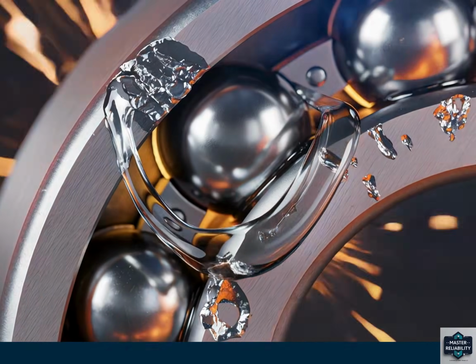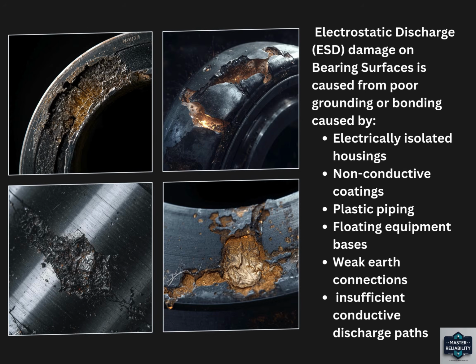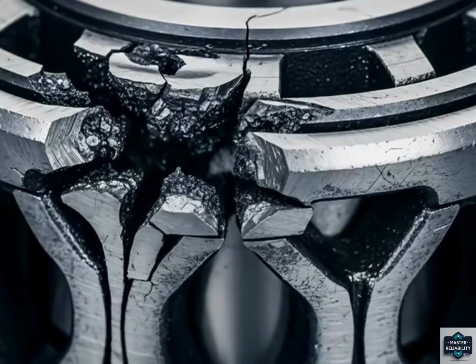Static charge commonly accumulates due to poor grounding or bonding caused by electrically isolated housings, non-conductive coatings, plastic piping, floating equipment bases, weak earth connections, or insufficient conductive discharge paths.